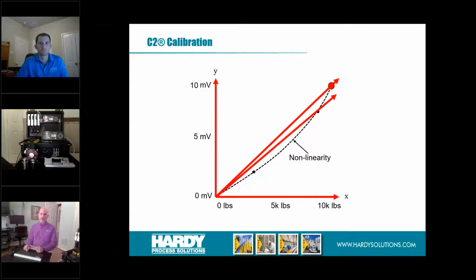There are a couple of problems that are not captured. There's actually 3 things really that are not captured. One is the hysteresis. So just because it came on this particular line the first time, on the way back down, it may have a little bit of a shift. Or the next time that you load it up, you may have a little bit of a shift in there. There's also a third problem that I can't really put on this graph, and that's called creep. What creep is, whenever I load the scale with, let's say, 10,000 pounds and I let it sit, that metal is going to settle. It will be a very miniature amount, but it's still going to settle. It's going to shift your readings a little bit.